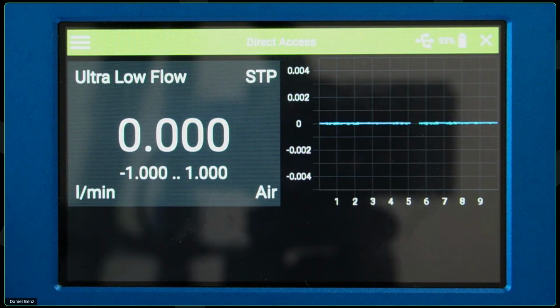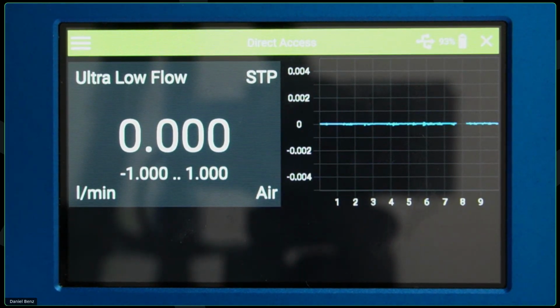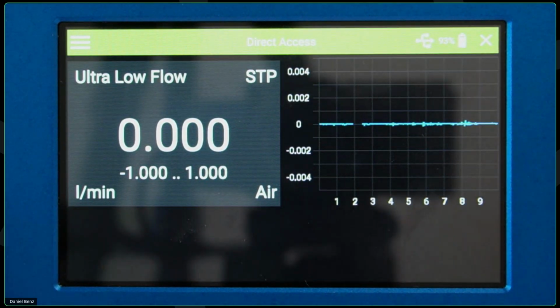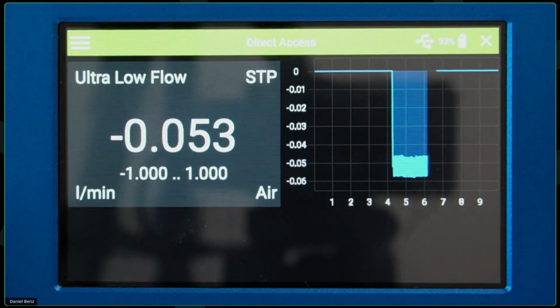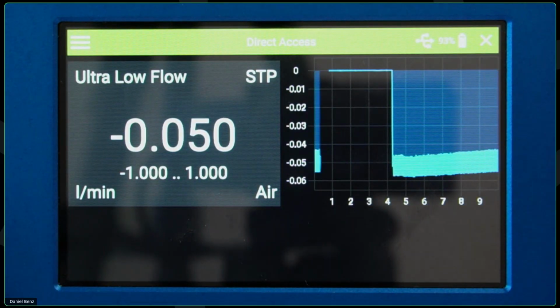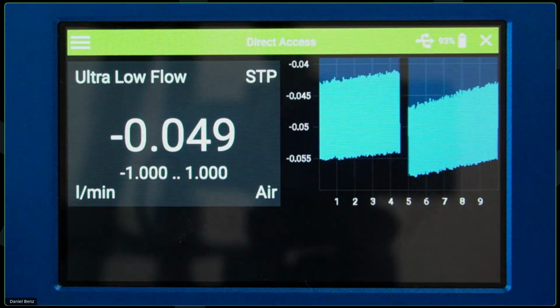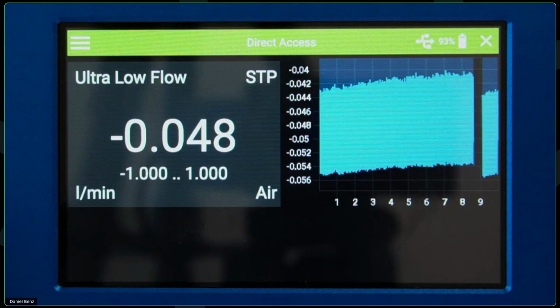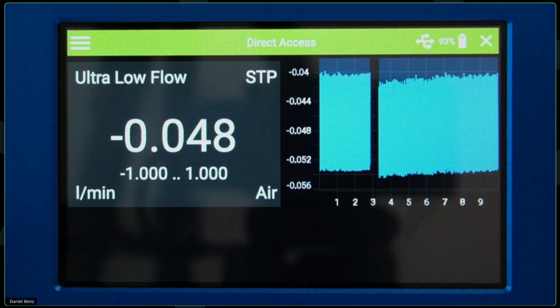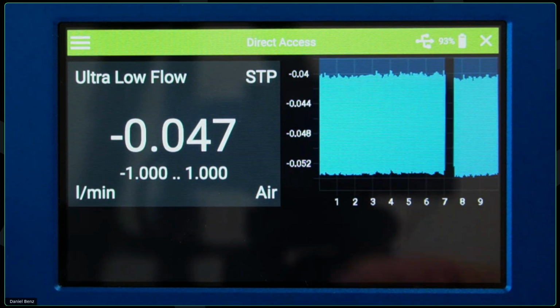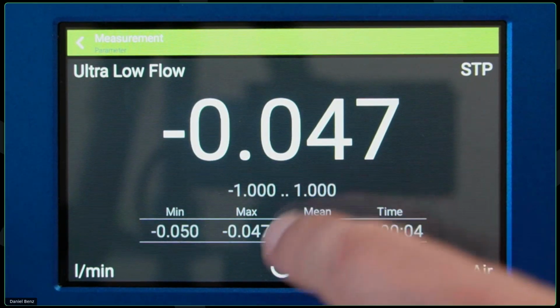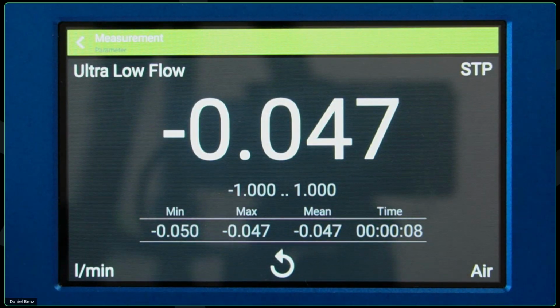So I can see now on the screen my ultra low flow and also the waveform next to it. So I don't have the sensor connected yet, but that's what I'm going to do next. So now you can see there is no flow at all. But if I connect this sensor to my ventilator, it's going to start sampling. And in just a little while, now you can see it is sampling with negative flow through my flow analyzer with about 50 milliliters per minute. So very, very low flow rates here. And I'm able to perfectly accurately measure these tiny little flow rates with the ultra low flow channel. I can also enlarge here and probably reset the statistics to see what range I am in. So it's between like 47 and 50 milliliters per minute.